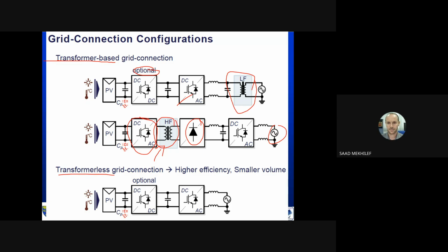So in terms of size, the high frequency based system is smaller. However, what you can see here, we have added another conversion stage, which is the rectification. Okay, so we have added this. So we have added losses. So like I say, there is no one perfect topology that can give you everything. There are always merits and demerits, and then which one is better. So high frequency is good. However, we have introduced another stage, which is the rectification, which does not exist in the low frequency.